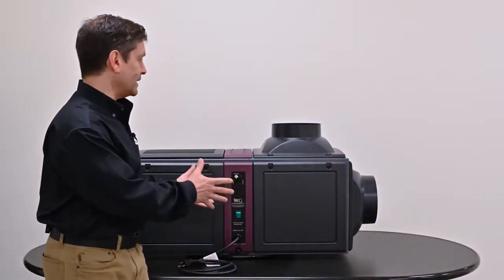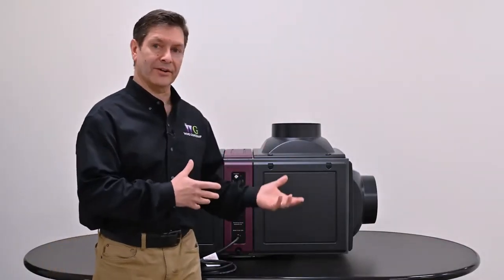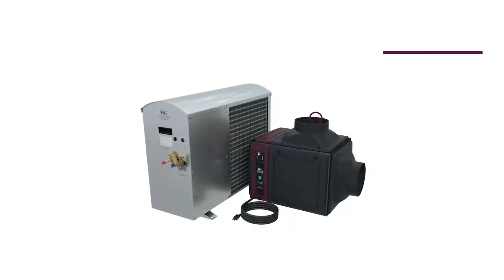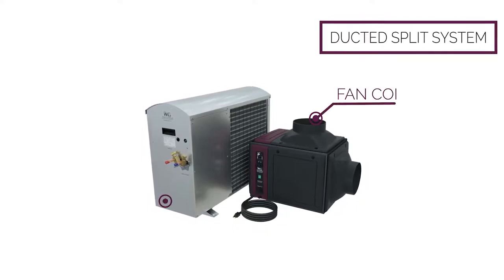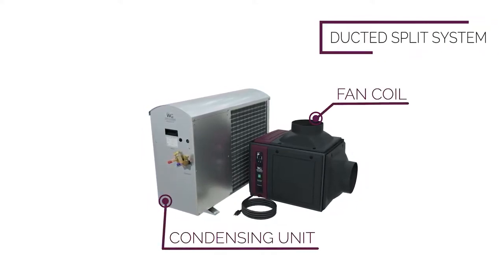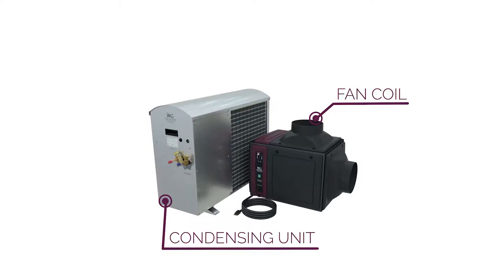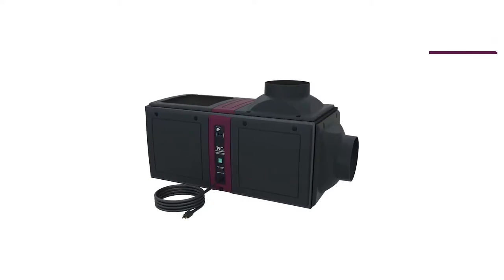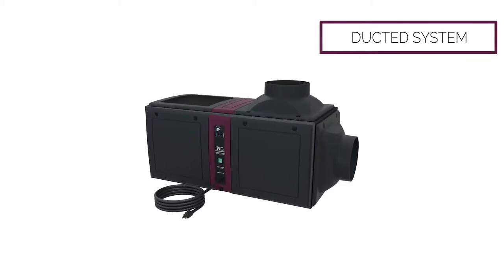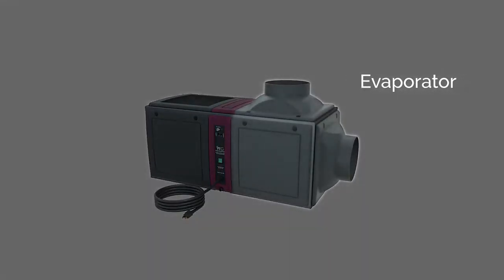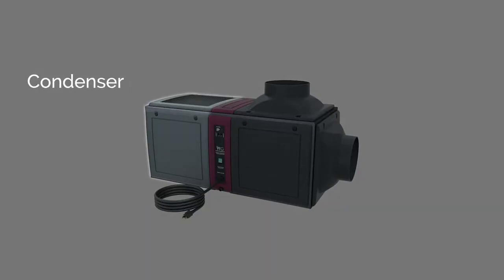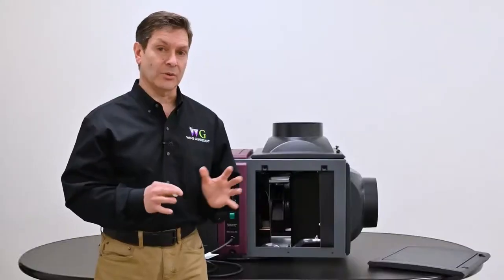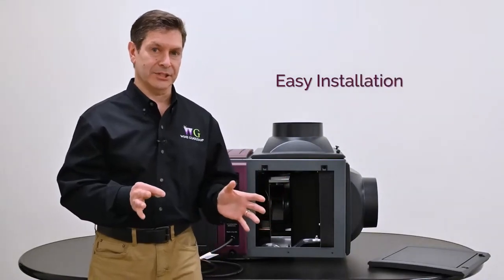This is our self-contained unit versus our Wine Guardian split systems. The Wine Guardian split systems can consist of a fan coil and a condensing unit, typically placed outdoors or in a large mechanical room. And then you would have the fan coil inside. This is a completely self-contained unit. It's really comprised of two compartments: an evaporator section, which ducts to and from the wine cellar, and a condenser section, which vents out into the mounting area. So that offers ease of installation.